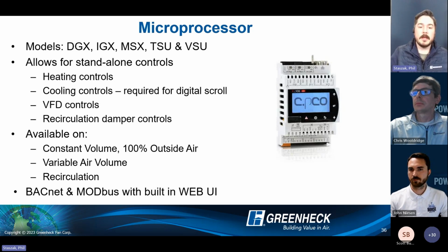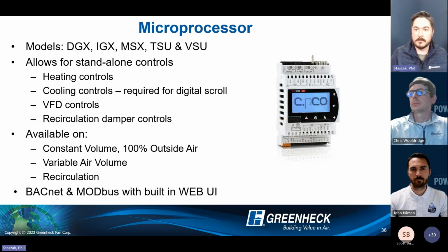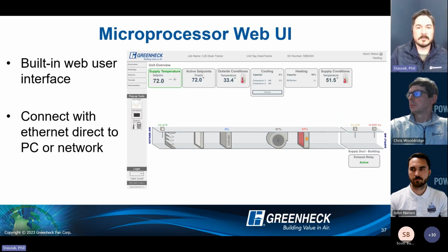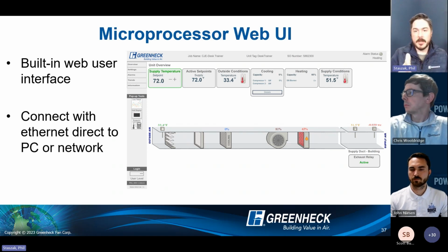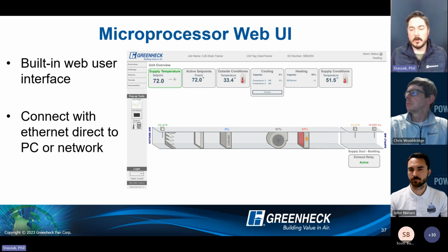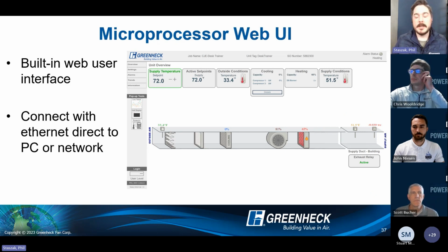They can be standalone and can also be operated with a building management system. There's always confusion there too. People think, oh, I got a microprocessor, I need a building management system. Not the case. These microprocessors can take care of themselves, with internal set points and very easy menu navigation to walk guys through starting up this equipment. So pretty slick stuff. Built-in web UI, or web user interface. This is what it actually looks like if you were to plug this in. This is built in, no charge. If you can connect an Ethernet cable, you can directly communicate with that unit, make changes, and view this little diagram that shows you the status of the unit: what your coil is doing, what your leaving air temp is, what your incoming air is. You can make changes, view alarms, and look at trend data and things like that.